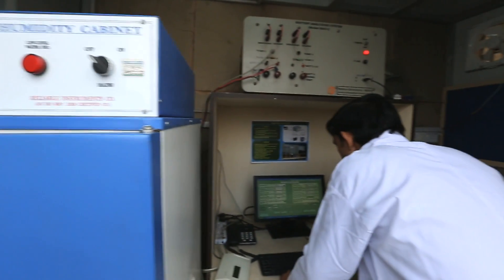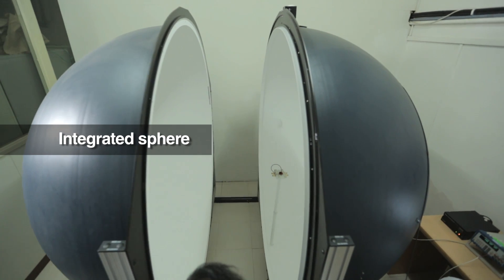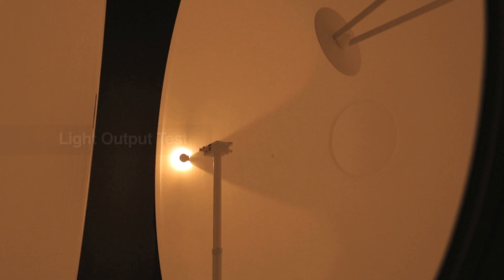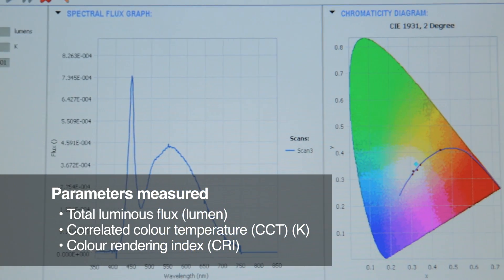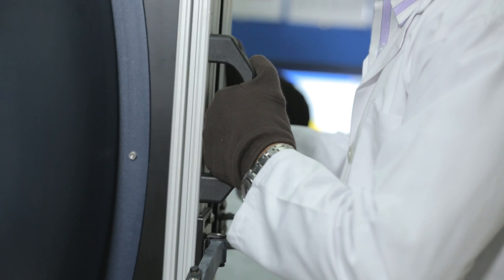The integrated sphere is used to assess parameters such as total luminous flux or lumen output, luminous efficacy, correlated color temperature, and color rendering index or CRI, which are very critical from the point of view of visual comfort.